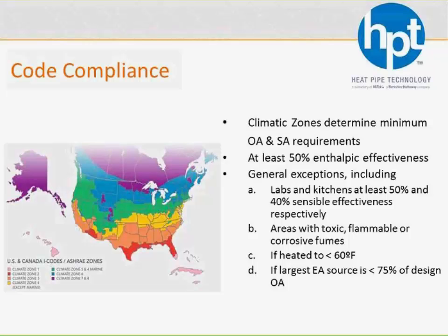So 90.1, most state building codes are based on some version of 90.1. You know, every 3 years they update it, but all of those are telling you that depending on what climate zone you're in North America, it gives you a nice chart and tells you that if you have this much outside air and this percentage of your supply air is outside air, then you have to have energy recovery. And not just any old energy recovery. It has to be energy recovery that's at least 50% enthalpic effective.